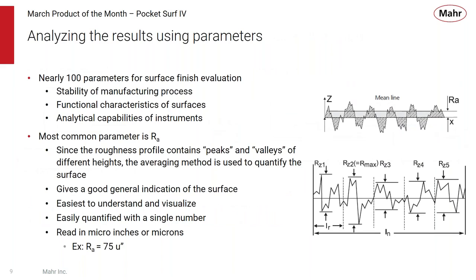Now, when you look at surface roughness, there are really nearly 100 parameters that can be used to evaluate surface finish. They serve different functions for checking the stability of the manufacturing processes and the functional characteristics of the surfaces. You can use these parameters to look at the analytical capabilities of the instruments. So there are lots of different parameters out there, but most things come down to what the average roughness is, and the most common parameter is roughness average. Since the roughness profile contains peaks and valleys, this averaging method is most commonly used to qualify the surface. It gives us a good general indication of what the surface is doing. It's easiest to understand and visualize. You can easily quantify it with a single number.